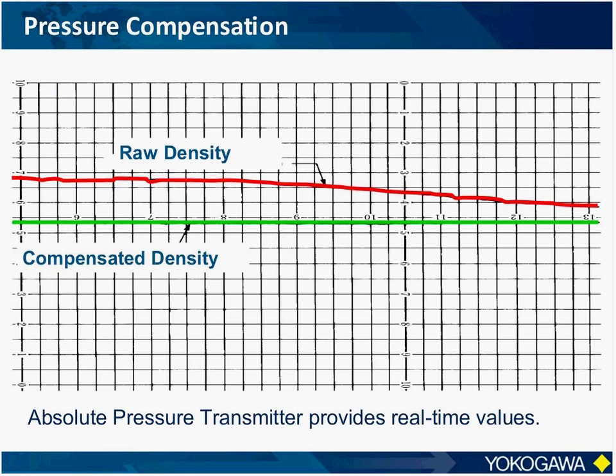Now, earlier we noted that some vibrating element systems feature a pressure transmitter to monitor the pressure of the sample gas. Once again, this allows the calculation of a raw density value at process pressure, but it'll also allow the instrument to calculate a compensated density value at a standard reference pressure. Typically, this is at 1 atmosphere of pressure. This also allows the sample gas to be introduced at a fairly large range of process pressure, and this reduces the amount of sample conditioning that's required before the gas is introduced to the instrument.